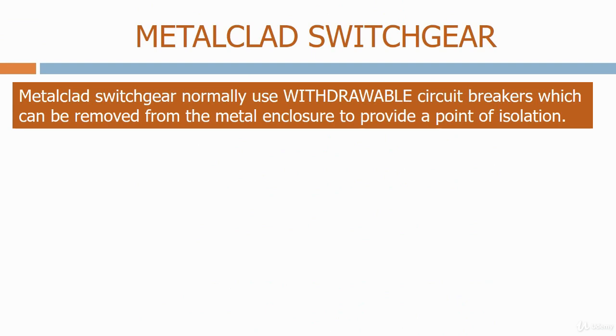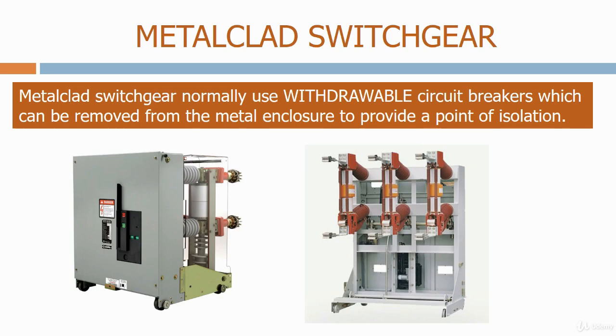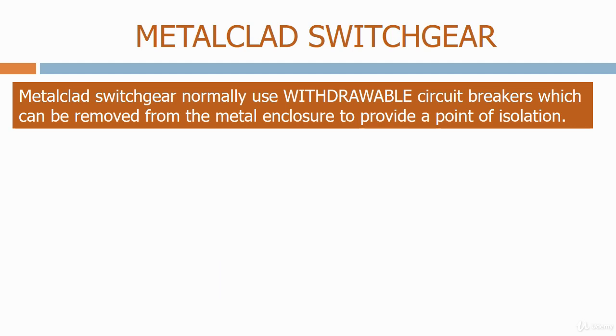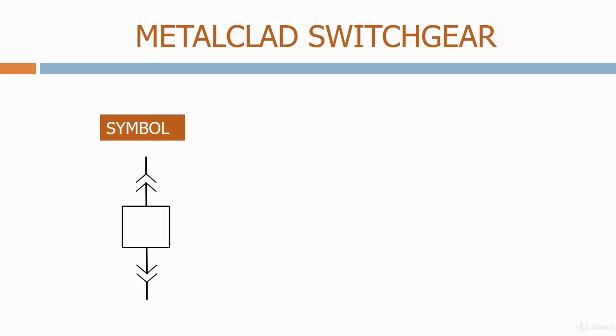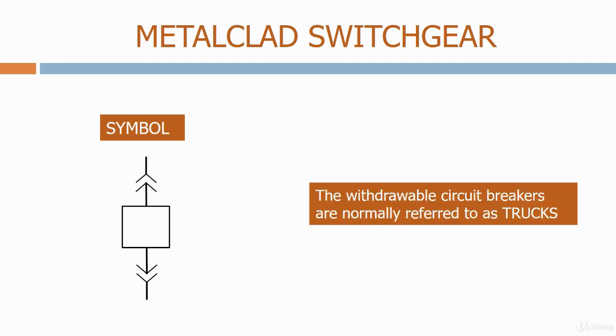Metal-clad switchgear normally use withdrawable circuit breakers, which can be removed from the metal enclosure to provide a point of isolation. Here's some typical examples of some withdrawable circuit breakers. Here's the normal symbol for a withdrawable circuit breaker. The withdrawable circuit breakers are normally referred to as trucks. Here's an example.